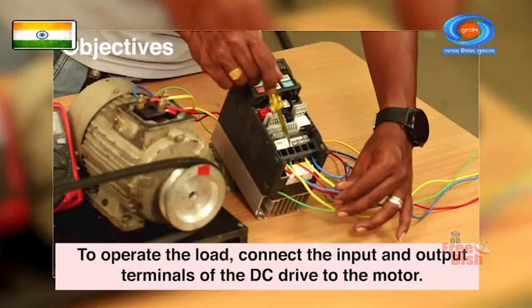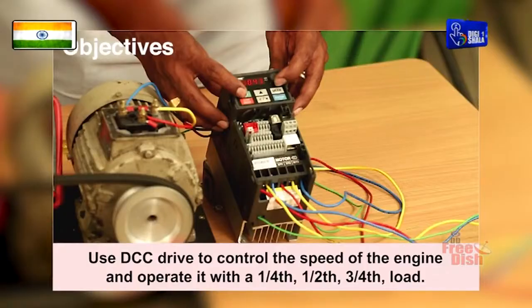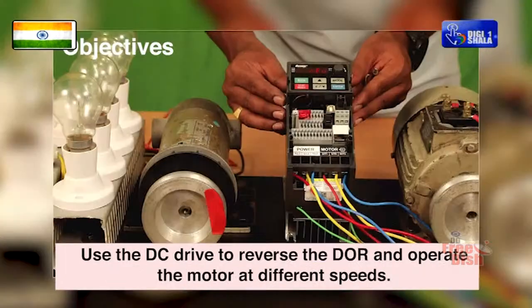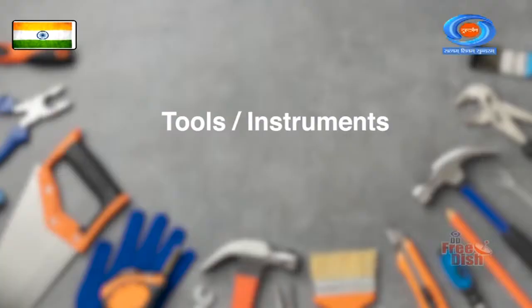To operate the load, connect the input and output terminals of the DC drive to the motor. Use a DC drive to control the speed of the motor and operate it with 1/4, 1/2 and 3/4 load. Use the DC drive to reverse the DOR, direction of rotation, and operate the motor at different speeds. Let us take a look at the tools and instruments required to perform DC speed control with thyristors or drives.